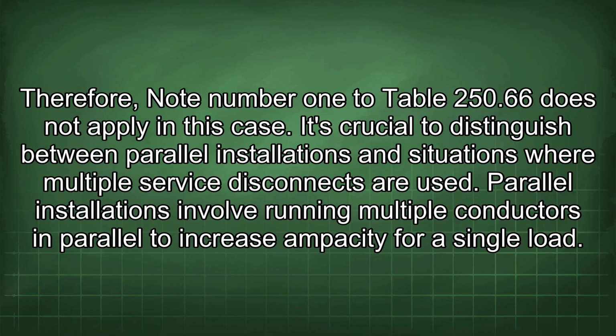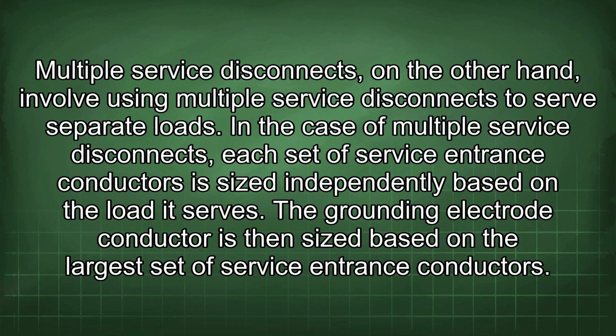It's crucial to distinguish between parallel installations and situations where multiple service disconnects are used. Parallel installations involve running multiple conductors in parallel to increase ampacity for a single load. Multiple service disconnects, on the other hand, involve using multiple service disconnects to serve separate loads. In the case of multiple service disconnects, each set of service entrance conductors is sized independently based on the load it serves. The grounding electrode conductor is then sized based on the largest set of service entrance conductors.